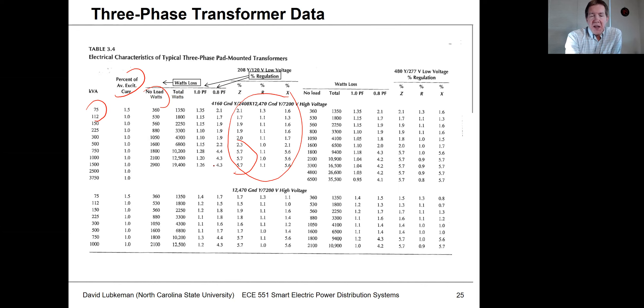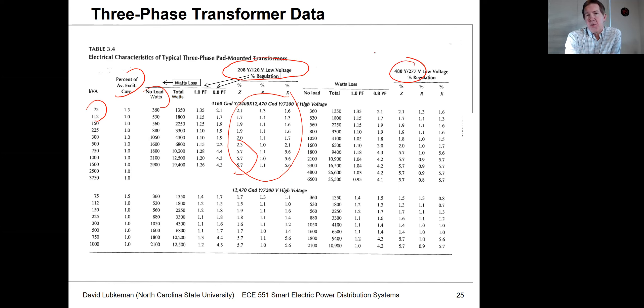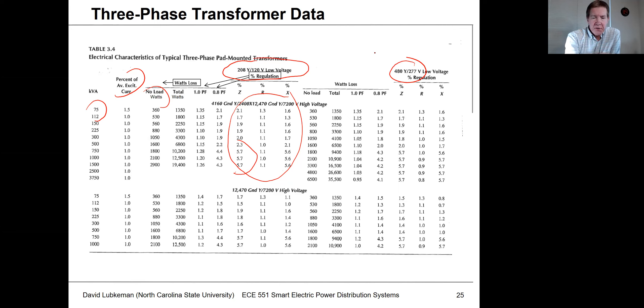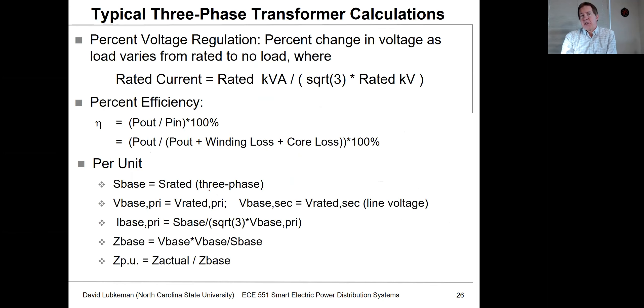For the larger transformers, impedances get up into the five to six percent per-unit range. Just like for single phase, we have different voltage levels to think about. On the left you see values for 208 volts line — more for commercial transformers. On the right, 480 volts line — for industrial applications with higher power process loads. I'm going to go ahead and stop here, and in the next video we'll go through some examples.